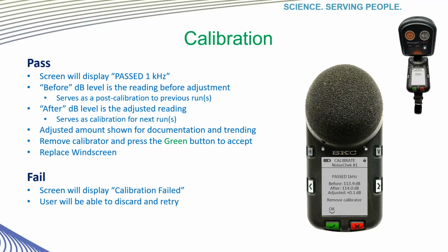The before value is the dosimeter reading before the calibration adjustment was made. This is important information because it serves as the post-calibration for previous runs using this dosimeter. So it basically closes your documentation loop for the previous run or runs since you last did a calibration. The adjusted amount is simply shown for documentation and trending purposes. The after value is the dosimeter reading after the calibration adjustment. This will serve as the calibration for your next measurement or your next measurements and runs.